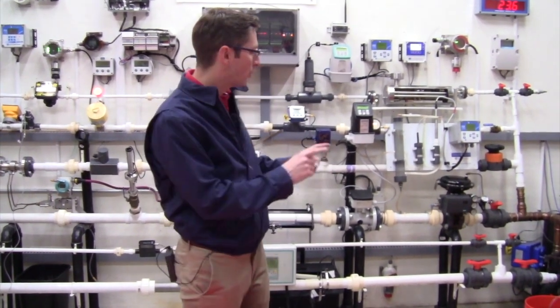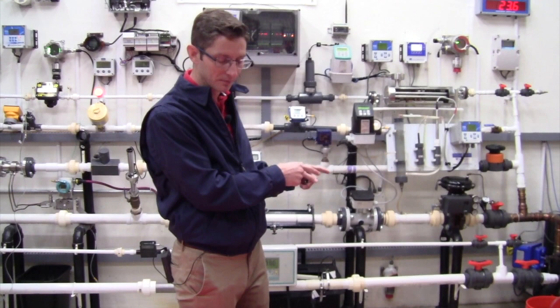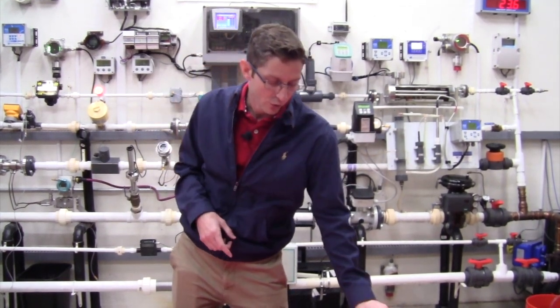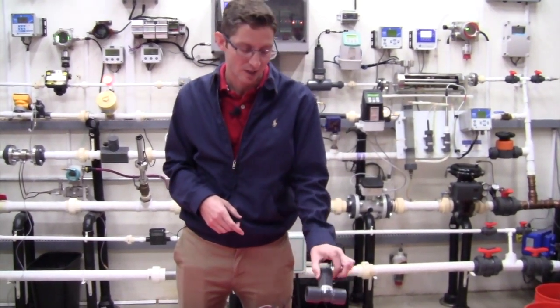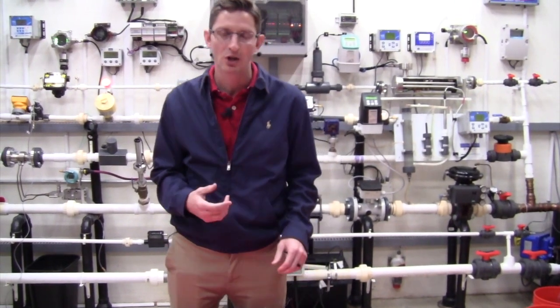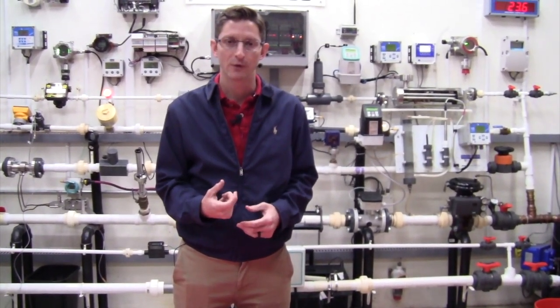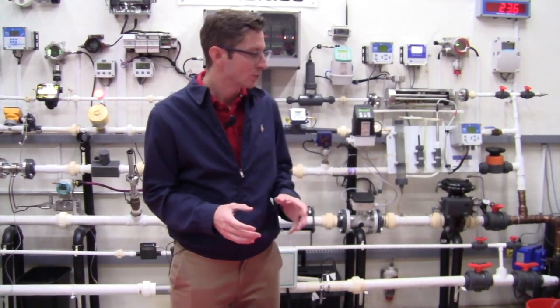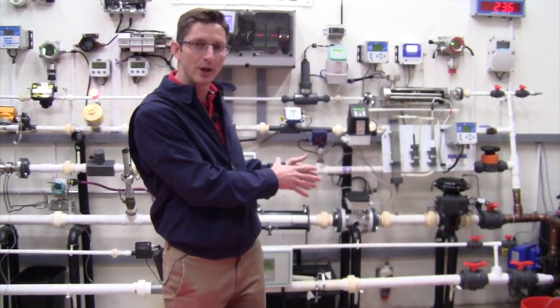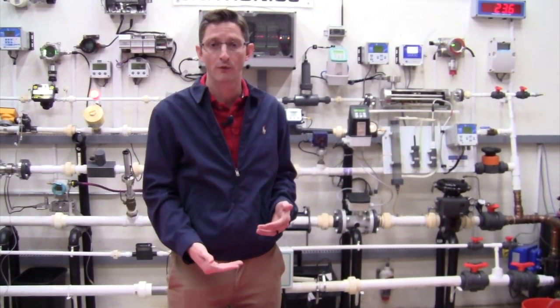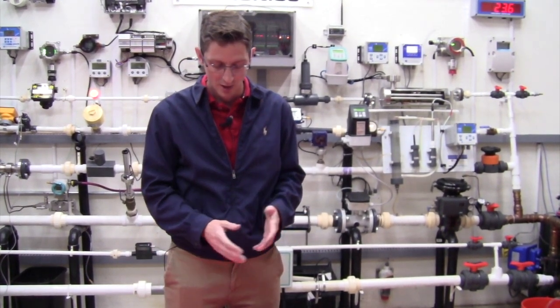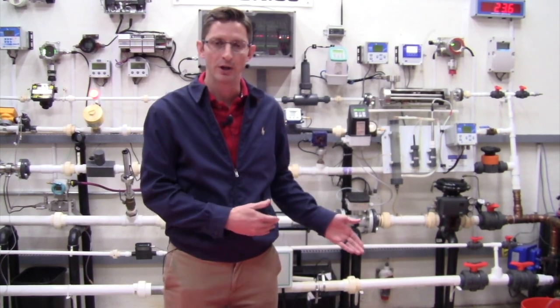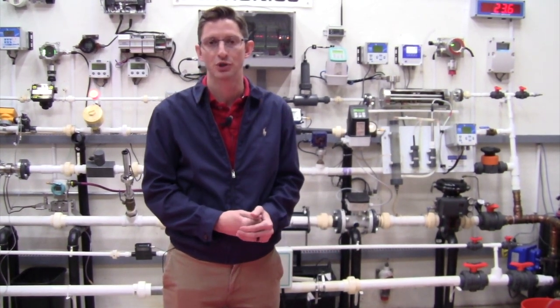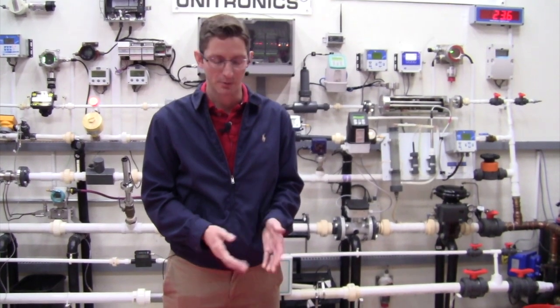Now, we have flowed water into this bucket. We also give you a K factor based on the T size, but those K factors are based on water. Your bleach or sodium hypochlorite has a slightly different specific gravity to water, so you always need to make sure that you run a calibration on bleach or whatever product it is that you are flowing through the paddle wheel. Once you've done this, you're now ready to use this meter, have your customers fill up jugs, and start billing them off of the meter.